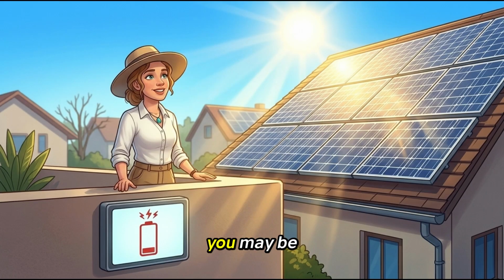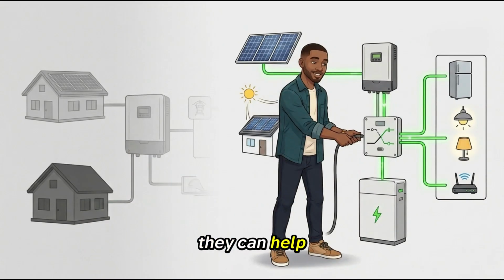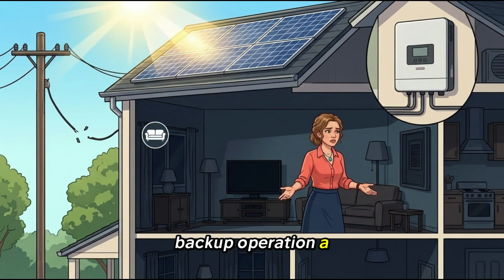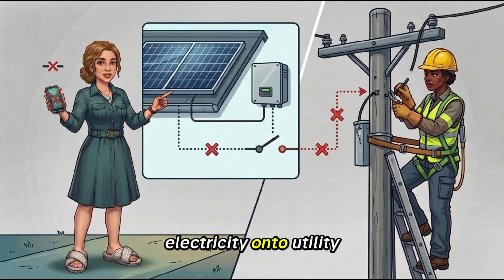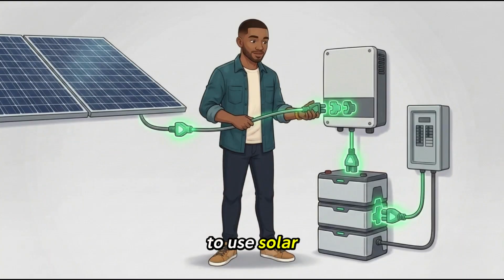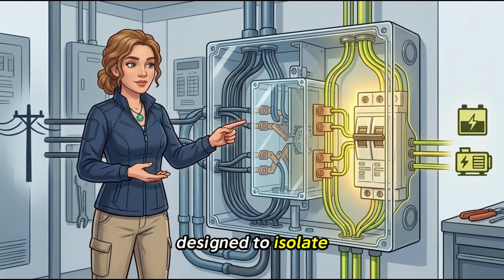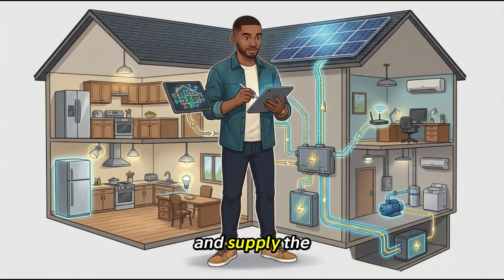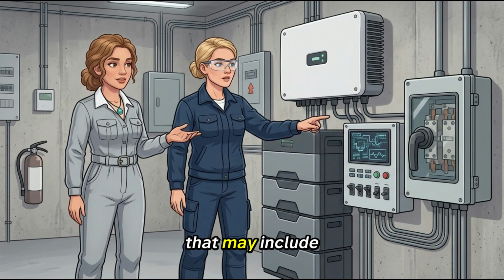At this stage, you may be thinking, solar panels solve the runtime problem. They can help, but only if the complete system supports backup operation. A normal grid-connected solar installation may shut down during an outage to avoid sending electricity onto utility lines. To use solar during a blackout, the system needs compatible equipment designed to isolate safely from the grid and supply the appropriate loads. That may include suitable inverters, storage, controls, and transfer equipment.